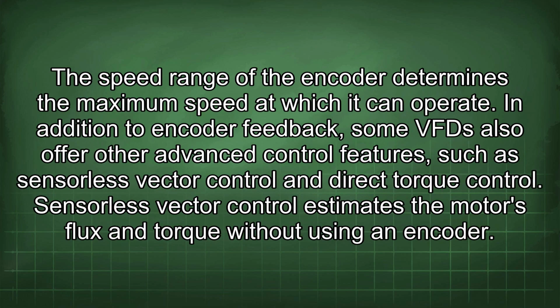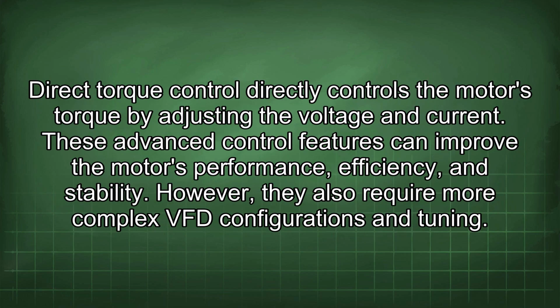The speed range of the encoder determines the maximum speed at which it can operate. In addition to encoder feedback, some VFD also offer other advanced control features, such as sensorless vector control and direct torque control. Sensorless vector control estimates the motor's flux and torque without using an encoder. Direct torque control directly controls the motor's torque by adjusting the voltage and current. These advanced control features can improve the motor's performance, efficiency, and stability.